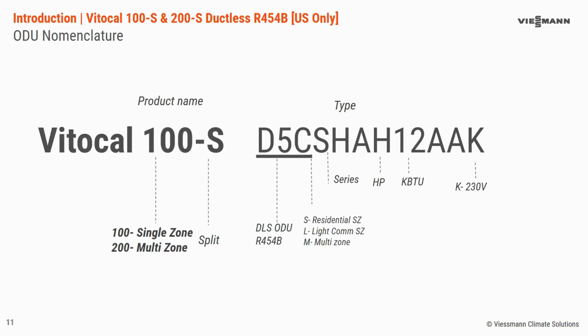The next big call out is on the model number. D5C is going to be the starting model for all outdoor units. That lets you know it's a ductless R454B outdoor unit. In my mind, I say D5C, D5 condenser, but you'll see that means clearly that this is an outdoor unit when you see that. The next letter will call out whether it's a single zone residential, single zone light commercial, or a multi-zone outdoor unit.